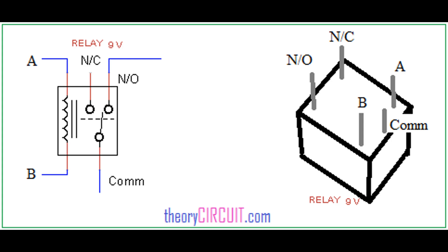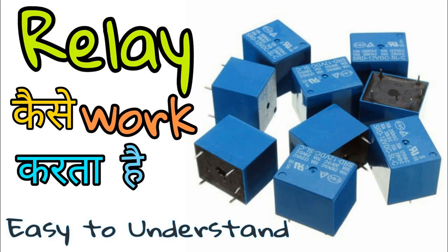Overcurrent Protection: Overcurrent relays are a common type of fault protection relay. They detect and respond to excessive current flowing in the circuit, which could result from a short circuit or an overload condition. The relay opens the contacts to interrupt the current flow and prevent damage. Overvoltage and Undervoltage Protection: Relays can monitor voltage levels and respond to overvoltage or undervoltage conditions. Overvoltage protection helps prevent equipment damage from voltage spikes, while undervoltage protection ensures that equipment operates within its specified voltage range.